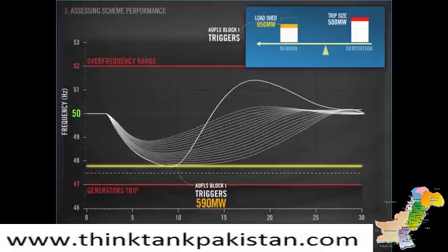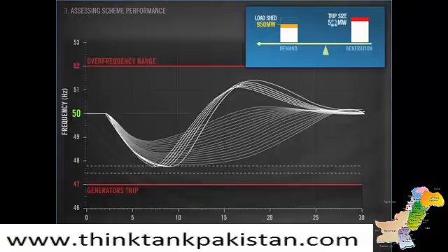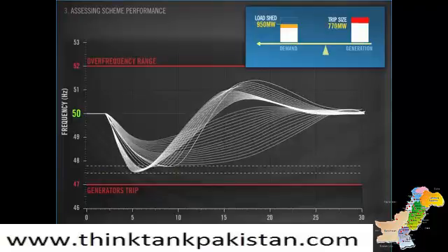As you can see from the seesaw, we are shedding quite a bit more than the system needs, which results in something we call frequency overshoot. In this case, the frequency rises above 50 Hz and is heading up towards 52 Hz before it's pulled back down, and that's the result of disconnecting too much demand from the system. You can see that as the event size increases, you get closer to the ideal in terms of the amount of load shed the system needs.